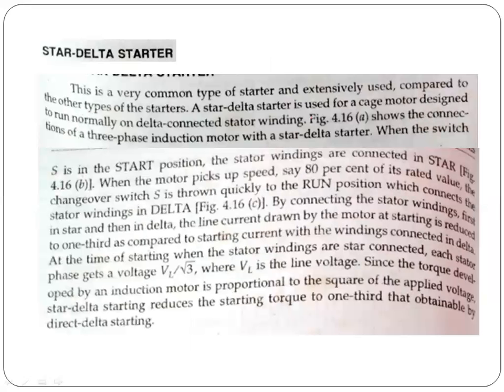Now the second type of starter we are coming to is the star delta starter. This is a very common type of starter and extensively used compared to the other types of starter. A star delta starter is used for a cage motor designed to run normally on delta connected stator winding. When the switch is in the start position, the stator windings are connected in star. When the motor picks up speed, say about 80% of its rated value, the changeover switch is thrown quickly to the run position which connects the stator winding in delta.